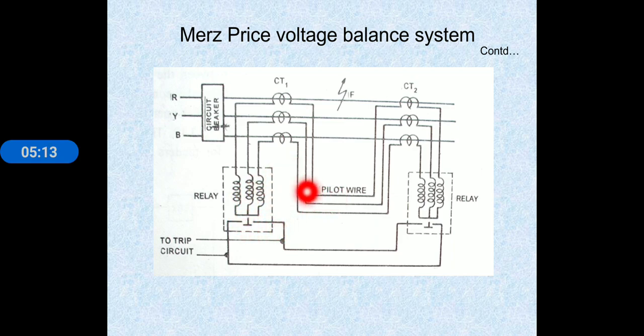Differential current is allowed to flow through these relays on both sides, and then it will trip the circuit. It sends the signal to the circuit breaker, and the circuit breaker isolates the faulty line. That is the general explanation. Once again I am explaining it. See here, it is a general schematic diagram for the Merz-Price voltage balance system.